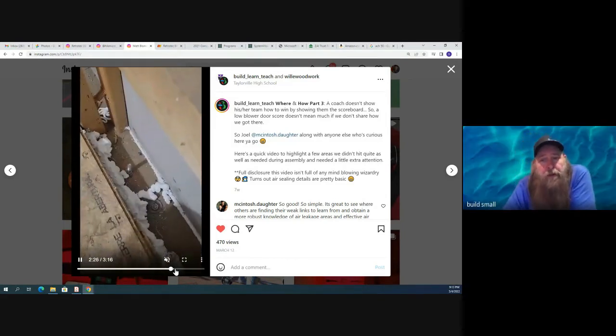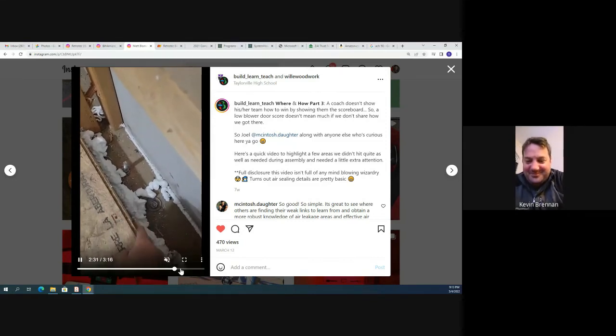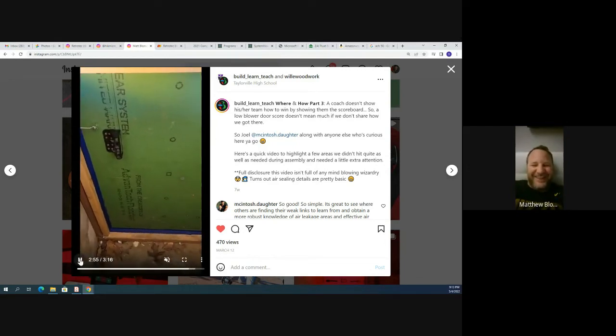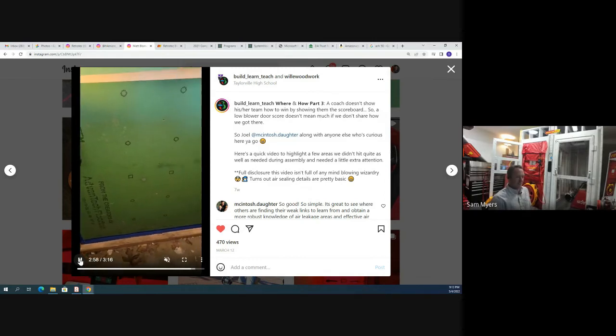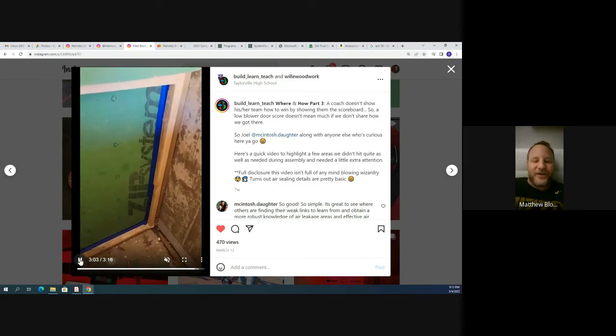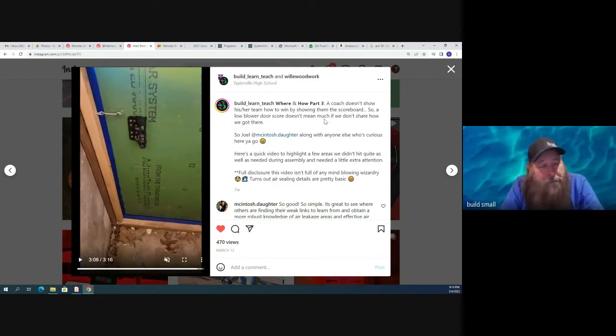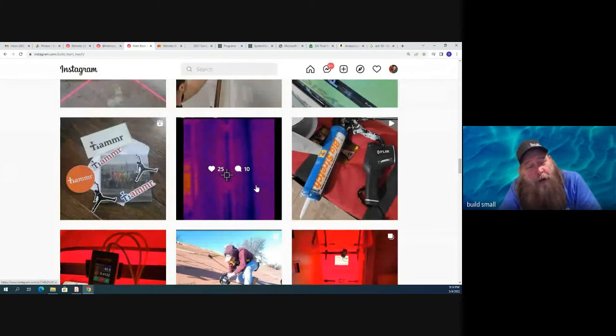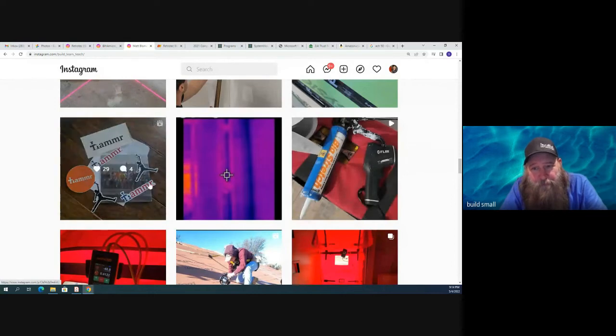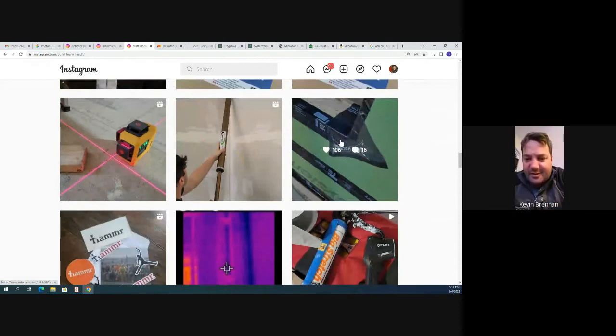So that's your lid. Now, HVAC contractors have a hard time getting duct leakage that low, and you did a whole house. No, the high school kids did it. I didn't do nothing. Is the air barrier at the ceiling or at the roof deck? Ceiling. We do all interior framing underneath the drywall, pre-hung. Cool. Matt is doing that thing where the drywall is the air barrier. Half the people in the industry don't like it because they argue against that, and he's proving that it is an air barrier. That's awesome.